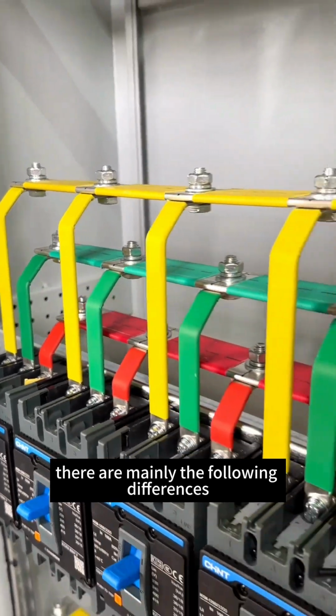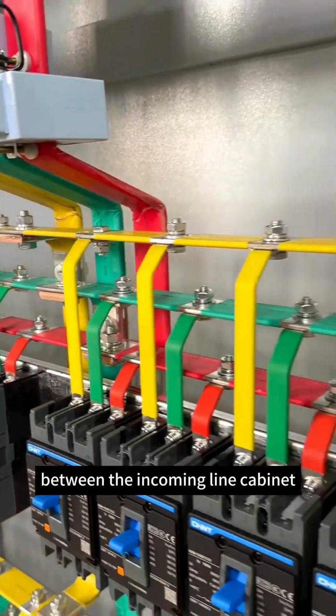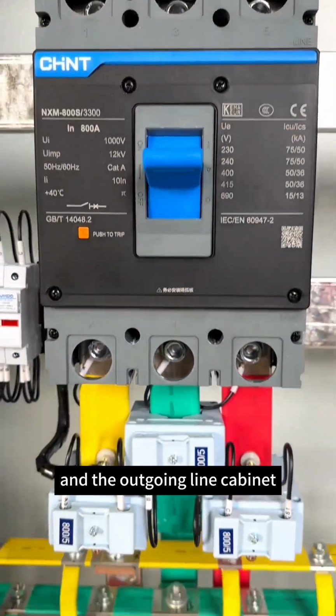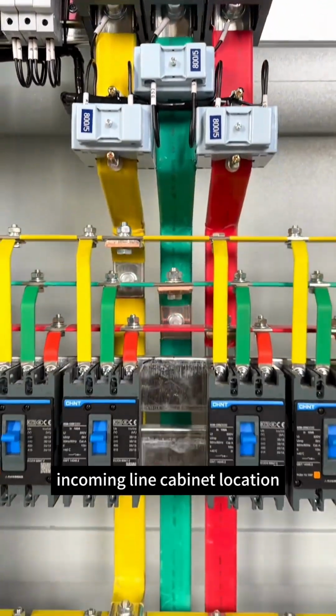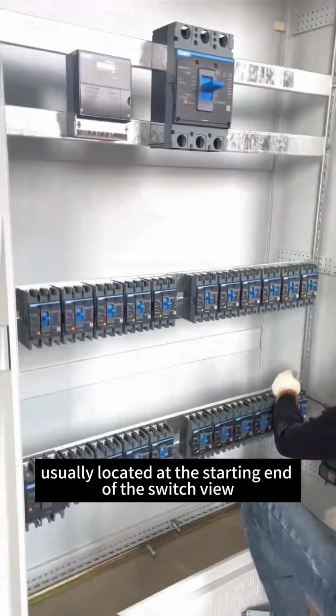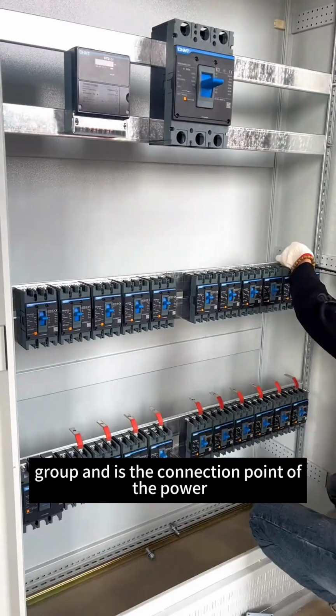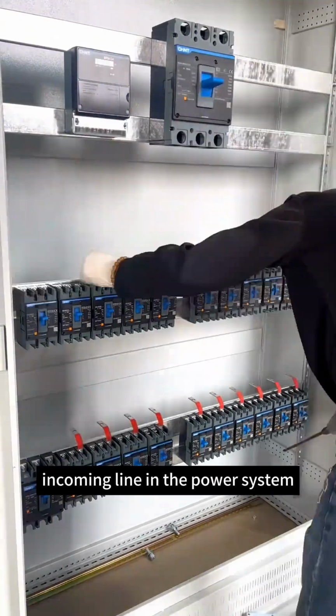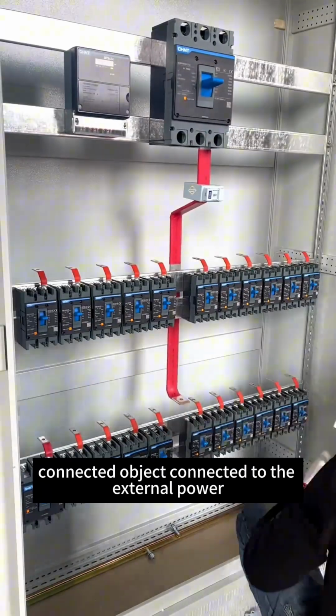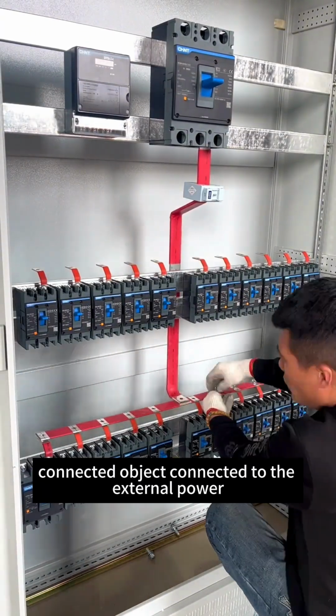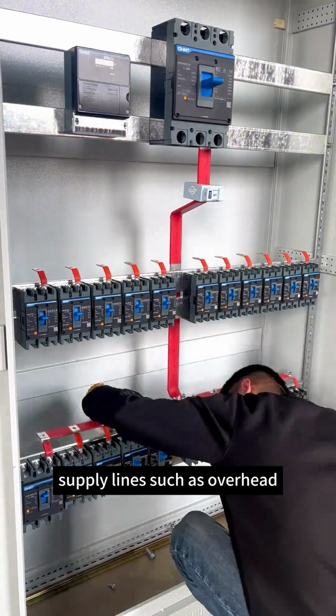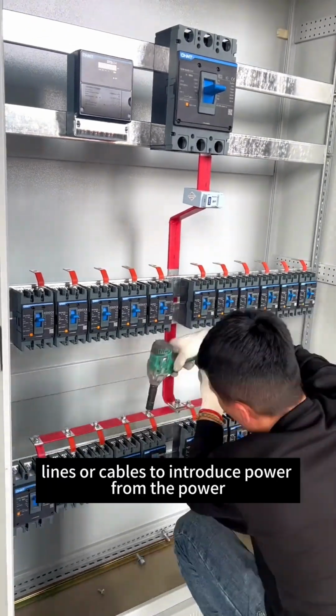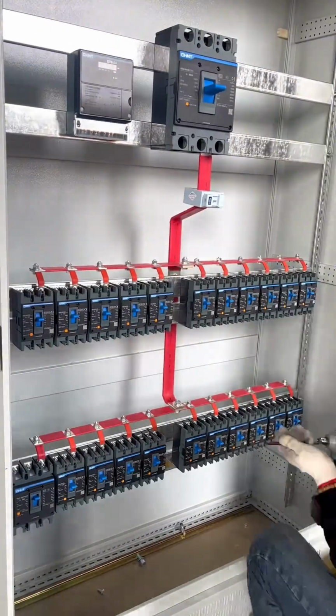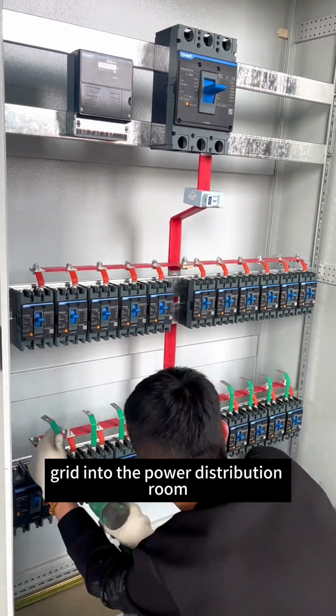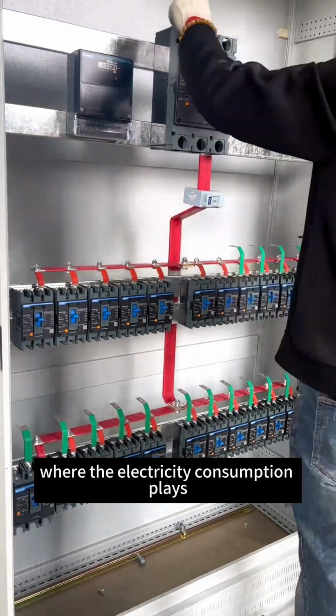There are mainly the following differences between the incoming line cabinet and the outgoing line cabinet. Incoming line cabinet: location is usually at the starting end of the switchgear group, and it is the connection point of the power incoming line in the power system. Connected object: connected to the external power supply lines, such as overhead lines or cables, to introduce power from the grid into the power distribution room where the electricity is used.